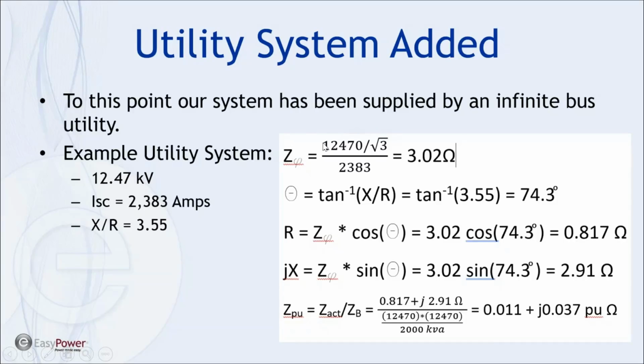And so we take the phase voltage. If the line voltage is 12470, we divide that by square root of 3, that gives us 7200. That would be the line to neutral voltage then. And the available fault current, phase to ground, or phase to neutral, 2,383 is the available fault current. So it's voltage divided by current that gives us impedance. So this gives us the magnitude of Z that has X and R, okay? This is the magnitude of Z.